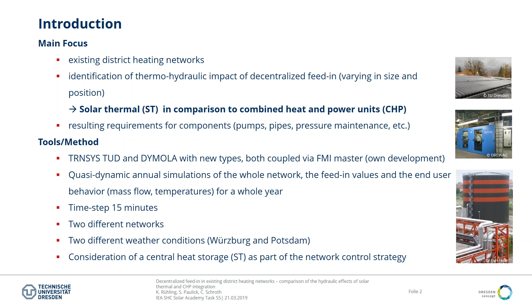The considered networks are two: Network G and Network B. Both are existing real systems in Germany. Network G is a third generation district heating network with supply line temperatures in winter up to 90 degrees centigrade and in summer up to 65 degrees centigrade - in most cases we had to reach feed-in temperatures higher than 70-75 degrees centigrade. Network B is a bigger one, a second generation meshed district heating network, with higher supply line temperatures - we had to reach feed-in situations for solar thermal purposes up to 110 degrees centigrade in spring and autumn.